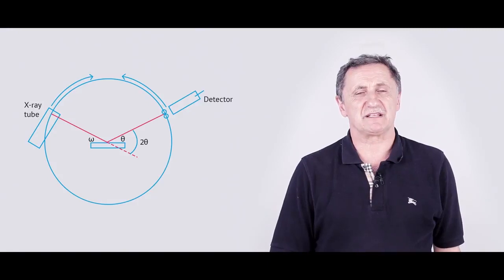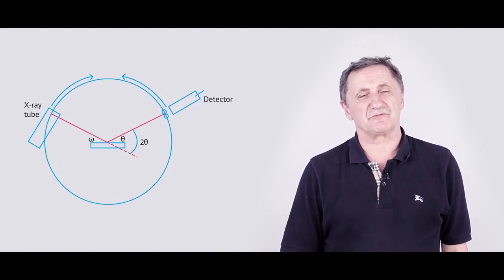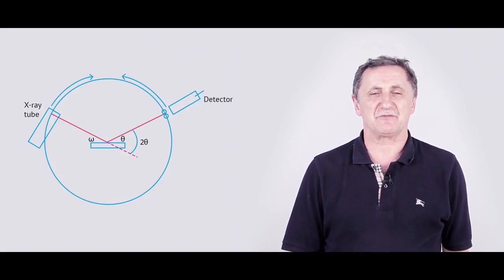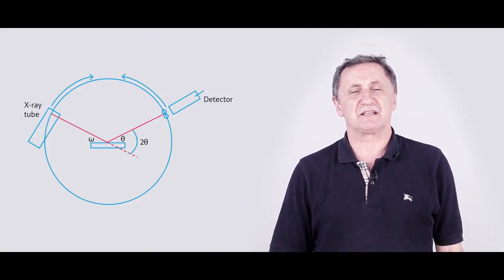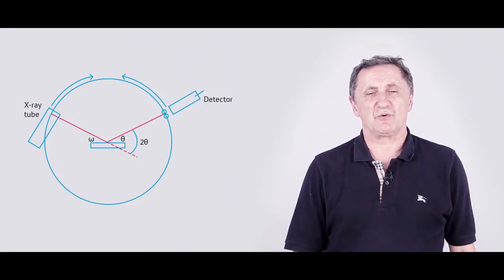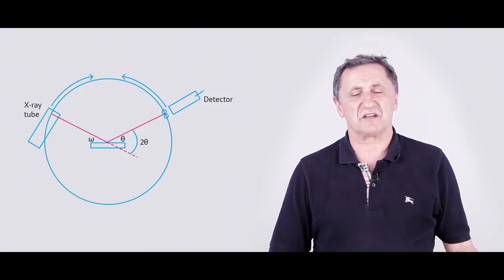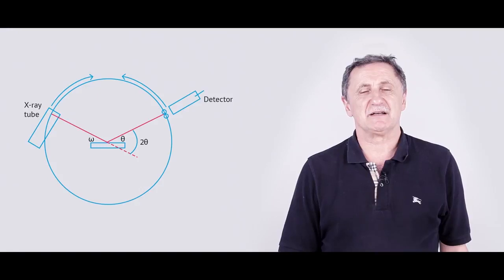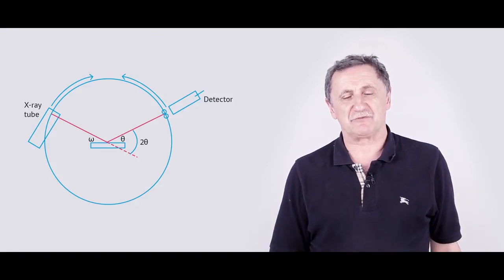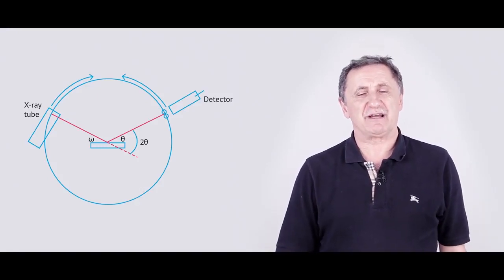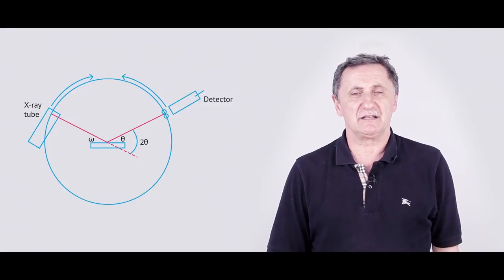Penetration of the X-rays inside the sample is on the order of 50 to 100 microns. It depends, of course, on the composition. So it means that if, for example, you are analyzing with XRD extremely thin coatings, let's say micron size coating or less, on some substrate, for sure you will also see the substrate. You have to take this into account.